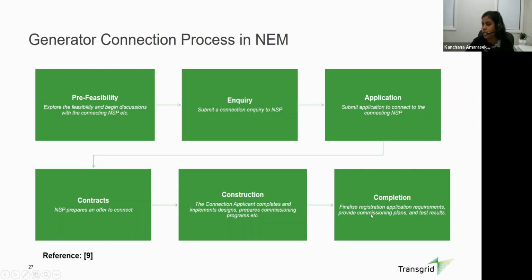Again, generator commissioning in Australia, the process is given in the NER, and basically it's a staged process. After generator registration, they can start. If it is a renewable generator, usually they have to start this testing with one inverter. Let's say it's a 100 megawatt plant, there will be three to four stages, and at each stage they have to do a number of tests to demonstrate that they can meet the GPS. And one key item is checking the actual plant performance against the model performance.